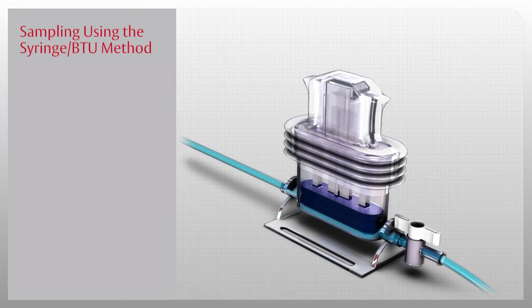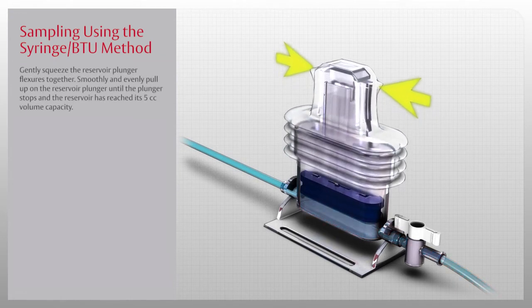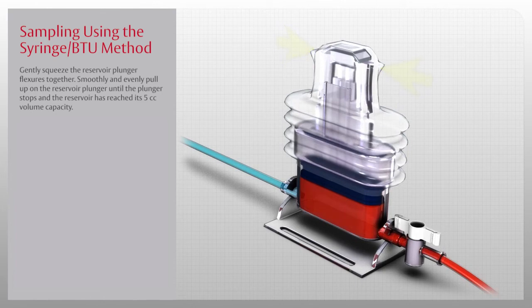Now that we have learned how to take a sample using the direct draw method, let us review the method of taking a sample using a syringe and blood transfer unit, or BTU. First, gently squeeze the reservoir plunger flexures together. Smoothly and evenly pull up on the reservoir plunger until the plunger stops and the reservoir has reached its 5 cc volume capacity. Once a clearing sample has been drawn, close the reservoir shutoff valve by turning the handle perpendicular to the tubing. This will further ensure that the sample drawn is from the patient and not the reservoir.